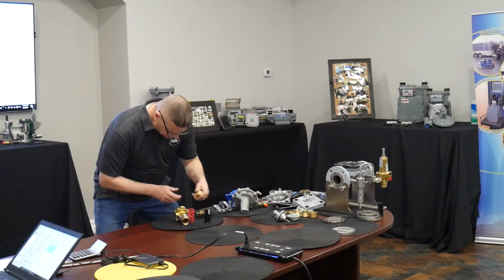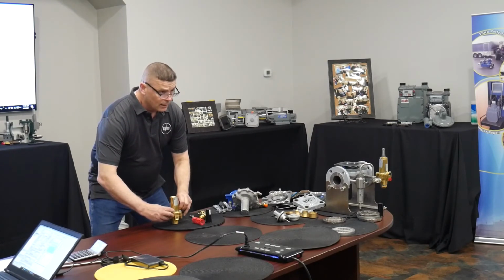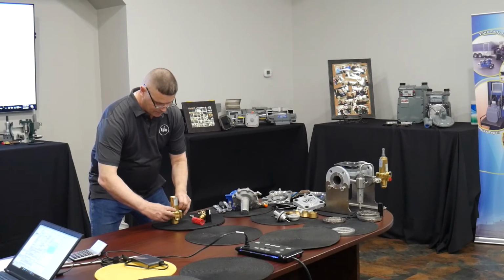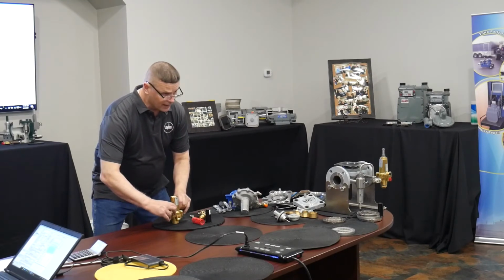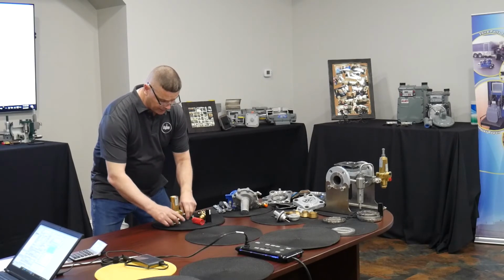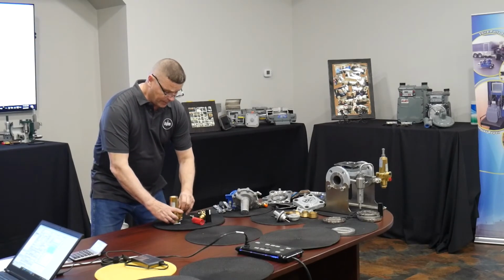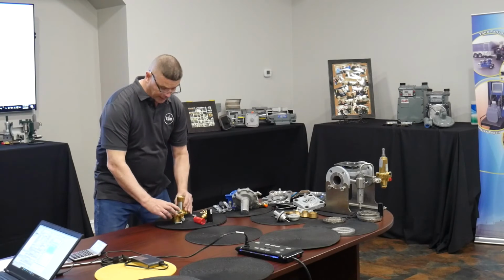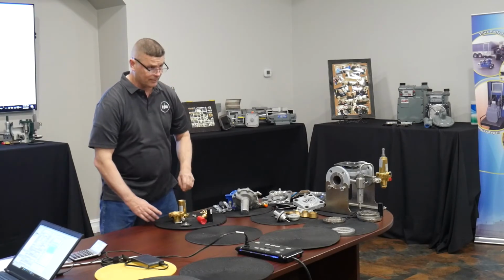Okay. All right. So pass these pilot parts around. Jeff, do you think the FlowSafe pilot, like the F100, is equivalent to the Series 20 pilot? The F100 shares some commonality with the Series 20 pilot. In my humble opinion, the Series 20 pilot design is superior, far superior. And if you ask me if a FlowSafe F70PR or F7000 would work effectively with a Series 20 pilot as its control, I would say absolutely yes, and I think we should demonstrate it and prove it.